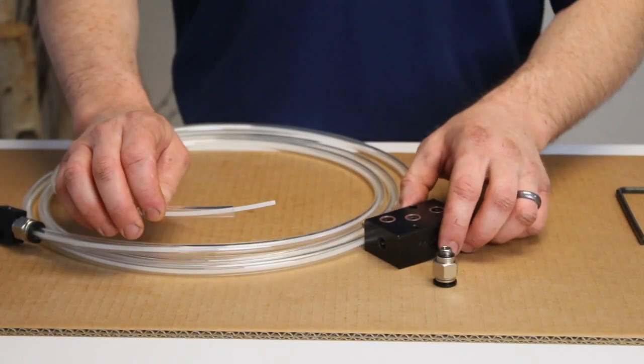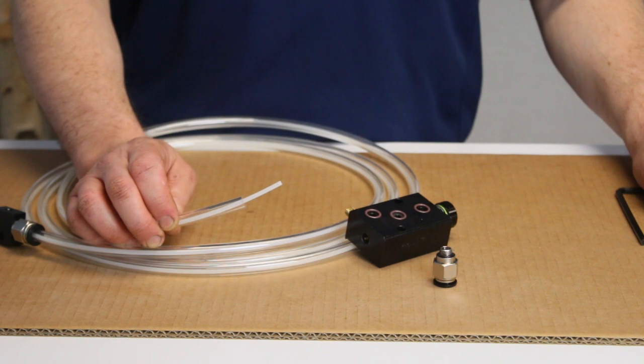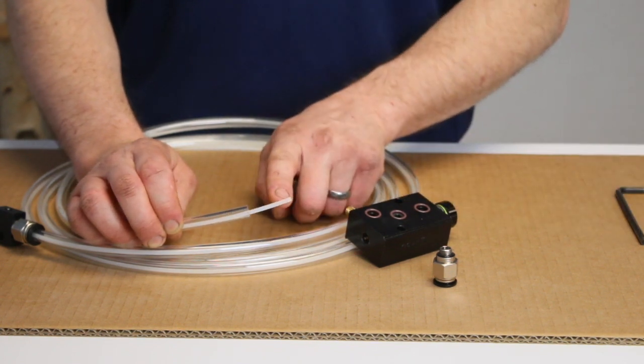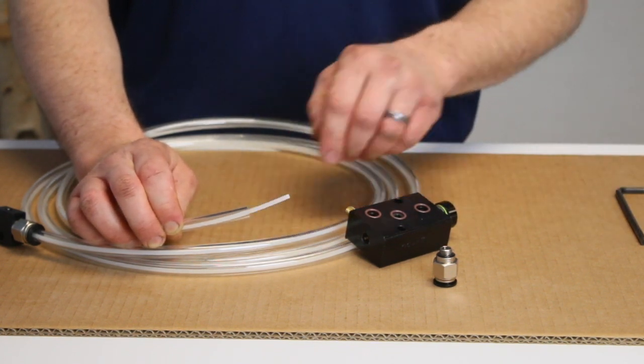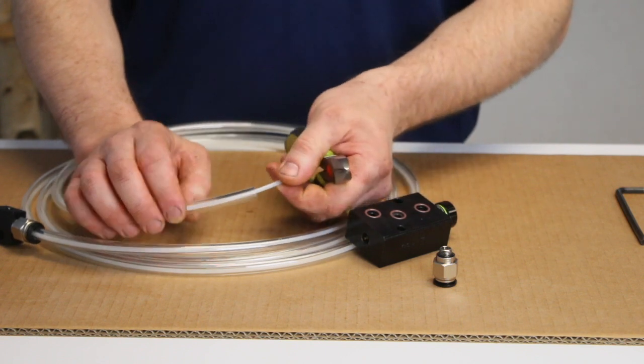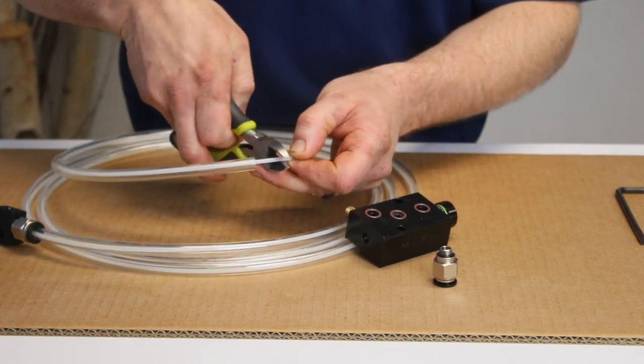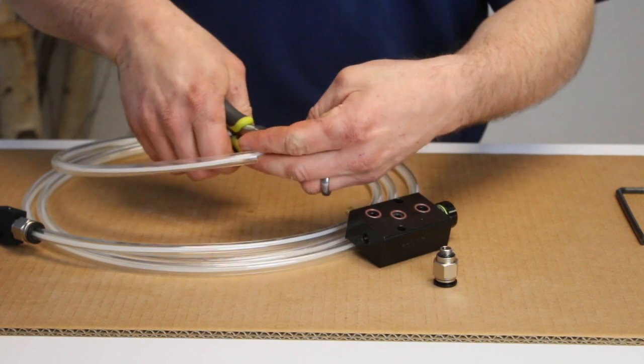With the hoses removed from the pump, you can then begin to work with the coaxial tubing. First begin by trimming back the capillary line. We always recommend trimming the capillary back to a clean section of tubing so you get a good seal on the outlet check valve housing when you reinstall it.